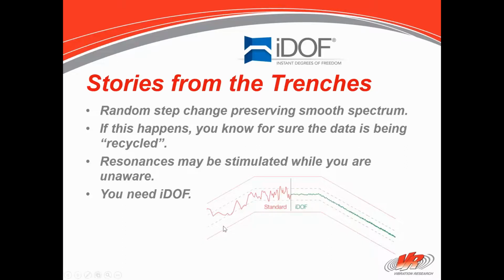And other controllers drew this very smooth line when a step change occurred. Well, that's impossible. It can't be done. And what's happening is they're recycling some of the old data, and if they step the level up 10 times, they recognize, hey, we need to draw a smooth line. So take all the old data, multiply it by 10, and say that's what it is. And that cannot be done.